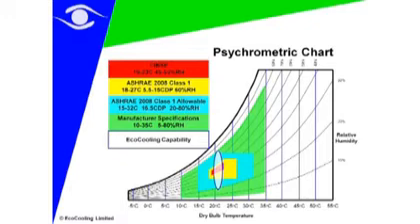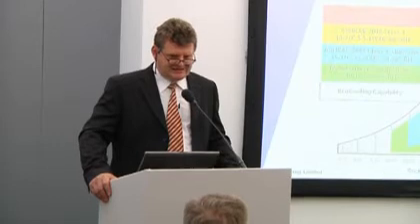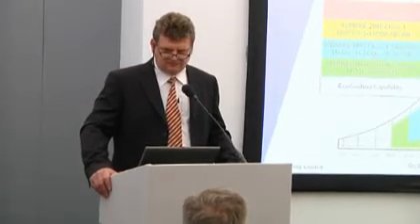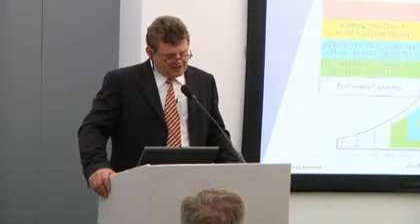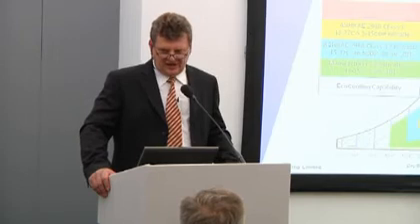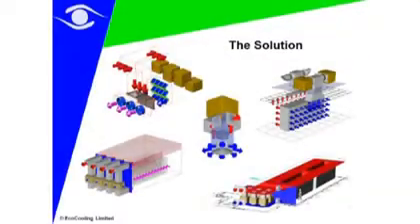If you take a ventilation system with evaporative cooling, you can put yourself into a zone there and provide 100% temperature compliance and about 99% compliance against ASHRAE Class 1. Now I'll explain how from that we can engineer and implement a system to actually exploit that.